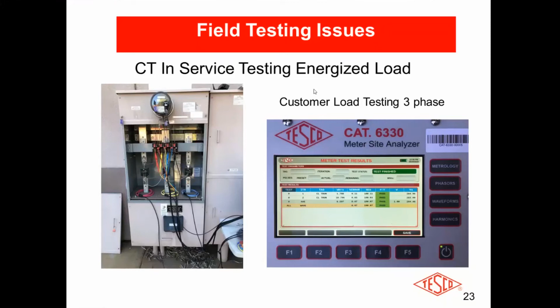That's definitely a given there. We know that. And then once we have that, we can get a CT test, which is primarily why we're doing this. So this information here is really why we're doing all of this testing, which is why this OSHA regulation is going to impact how we do this, how we approach it, the regulations that may be required, the safety issues we all are familiar with. We've talked about those. But this is what we're doing this for, so we can give you a valid and traceable result that you can then take back, document, and put into your system. Maybe go to the billing department and say, these are the CTs that we have, these are the tests that we have, these are the results that we have. We did it on this day, at this time. We can do it next year or the year after. And that really is the screen - that's the one screen that you'll be wanting to use, or that's the one bit of information that you will need.